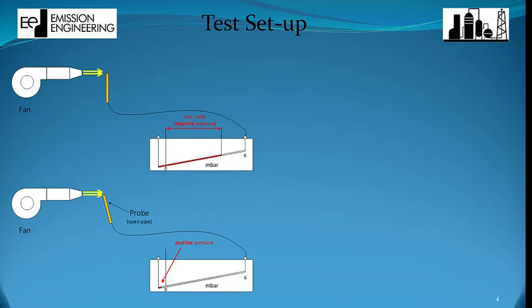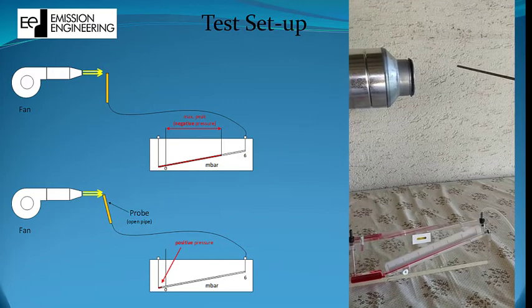There is an inclined pressure differential manometer, measuring the pressure between the dynamic pressure of the tubing and the static pressure in atmosphere. You will see that the measured delta P varies a lot with the angle that the tube is capped in respect to the flow direction of the air coming from the fan.